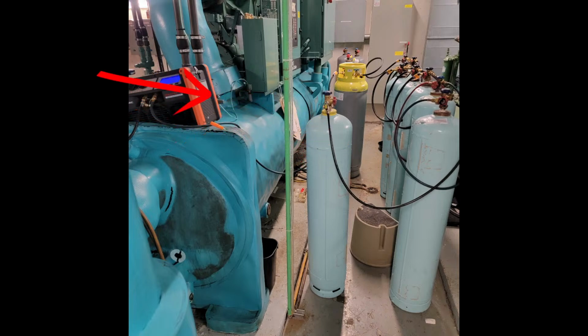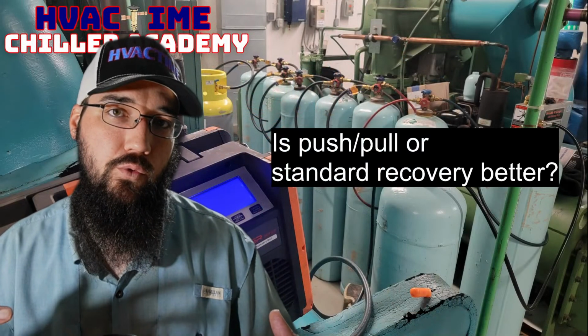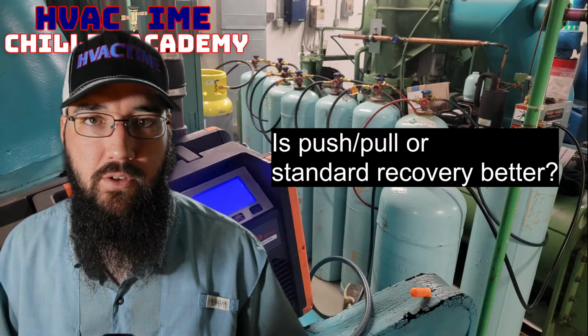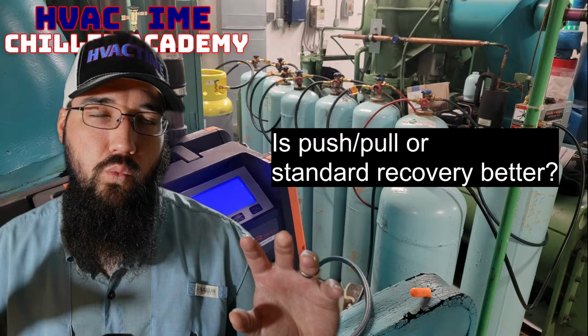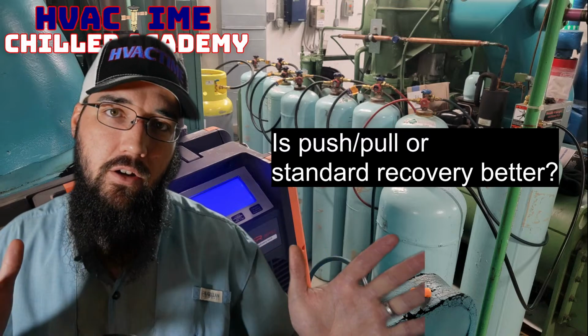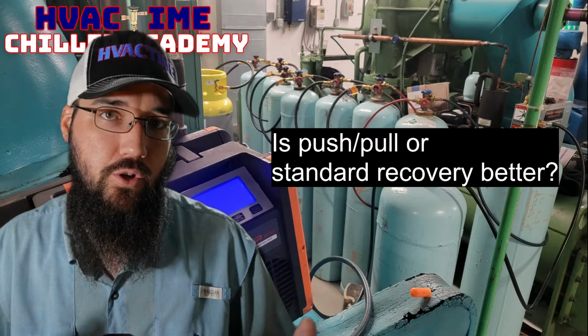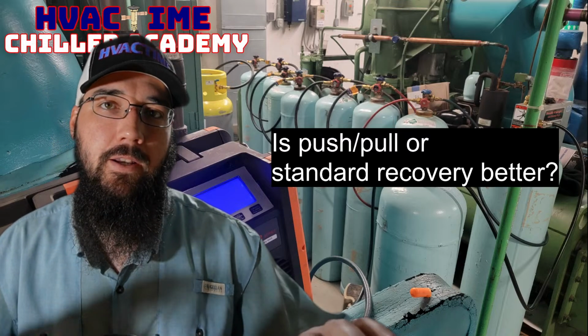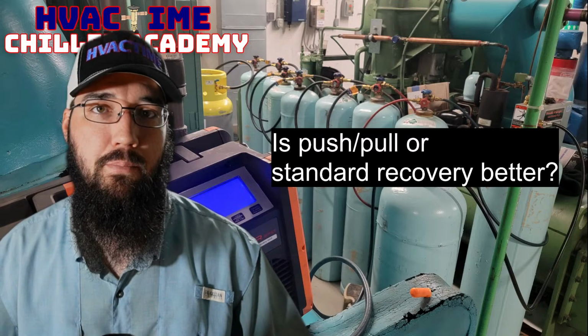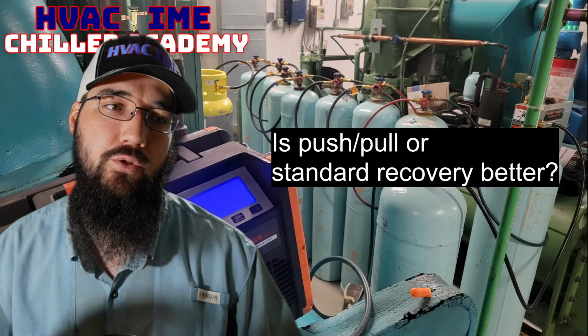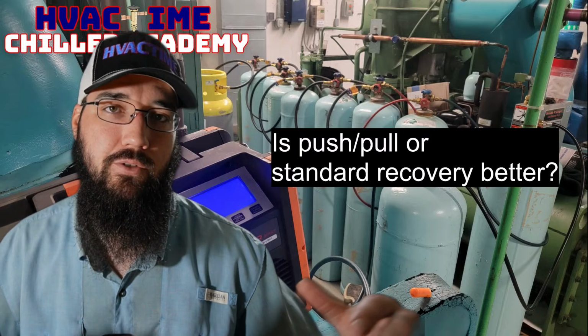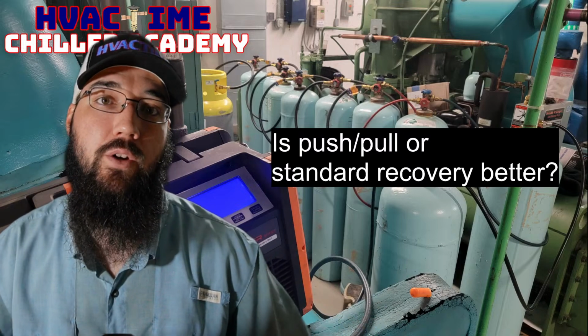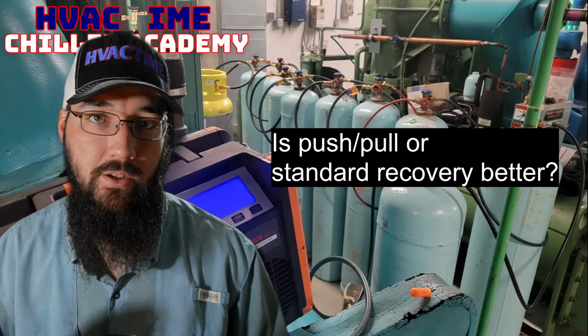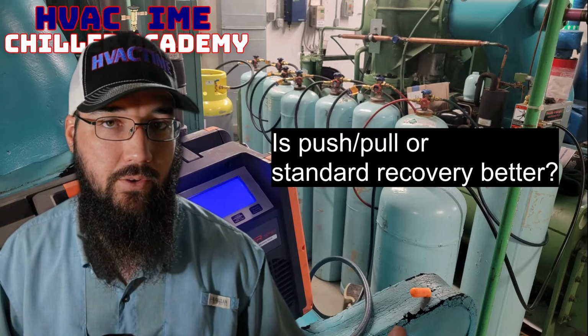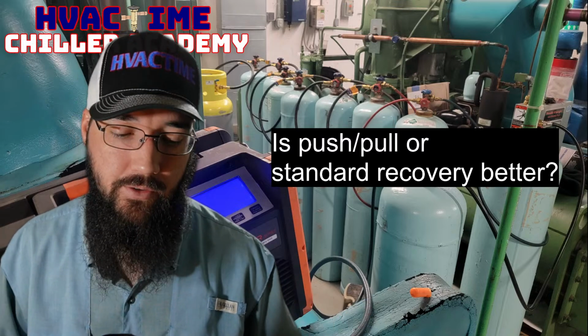We do this to maximize our ability to manipulate how the refrigerant flows. With a recovery machine, your speed of recovery or charging depends on the pressure differential across the pump. The lower we keep that differential, the less the pump has to work, and the smoother we transfer the refrigerant - whether into or out of the cylinder.